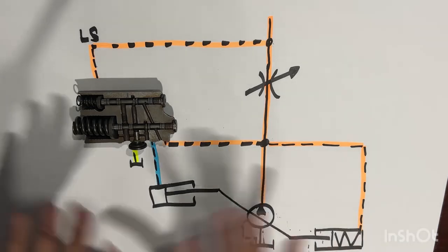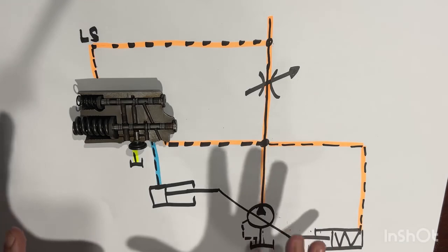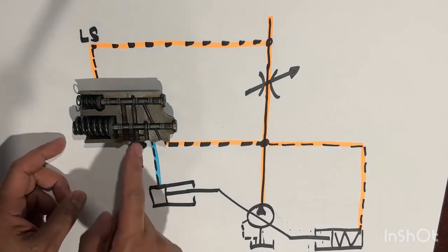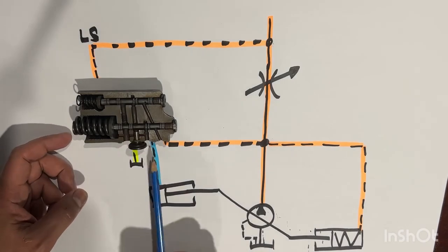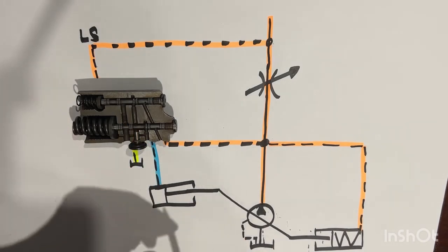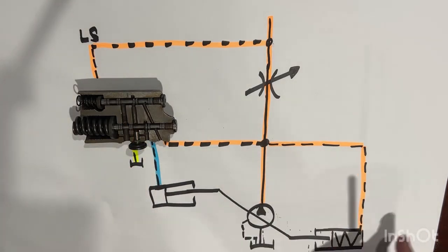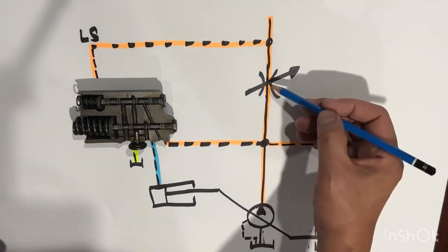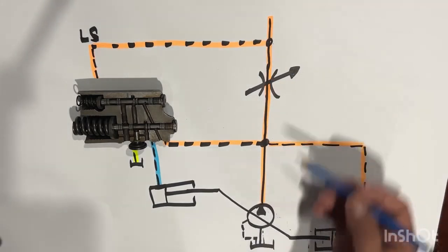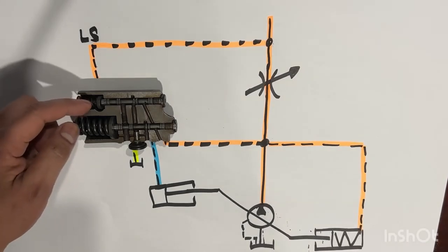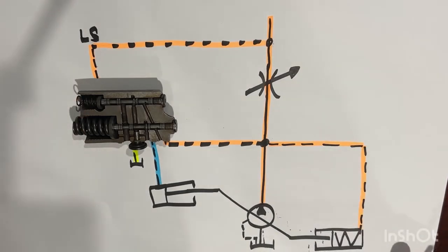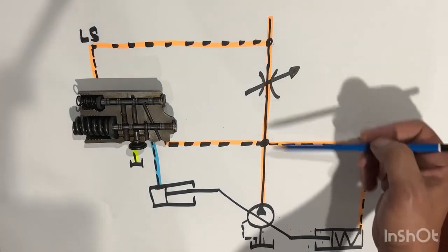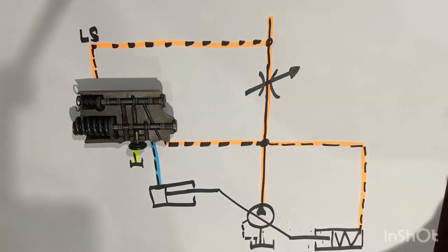Now in this condition, both spools are in position. The stroke piston is connected to the pump case, meaning the pump is in max displacement. That's condition number 1, the unregulated condition. This is 100% open, and the delta P spring here we set to 15 bar. The pressure is unloaded, meaning there's not much delta P across the throttle valve because this valve is fully open.